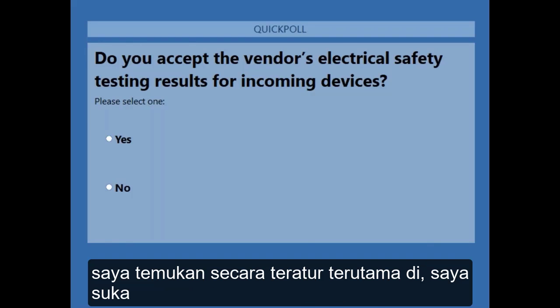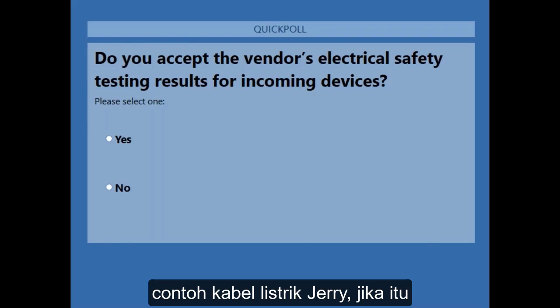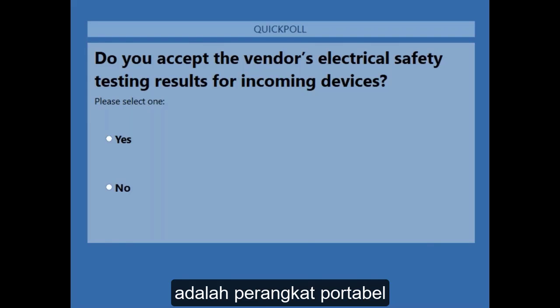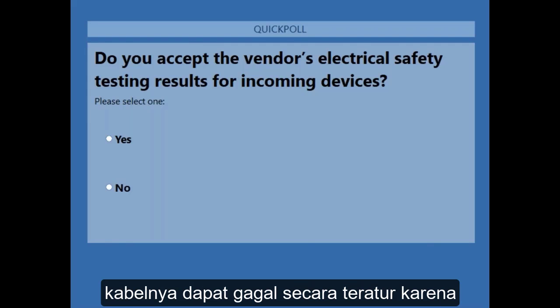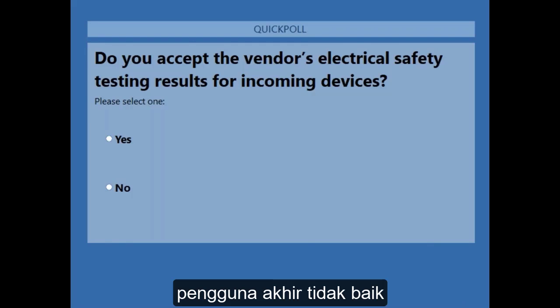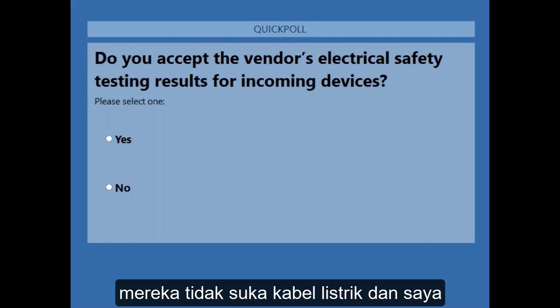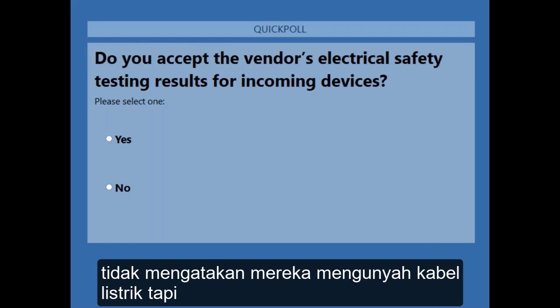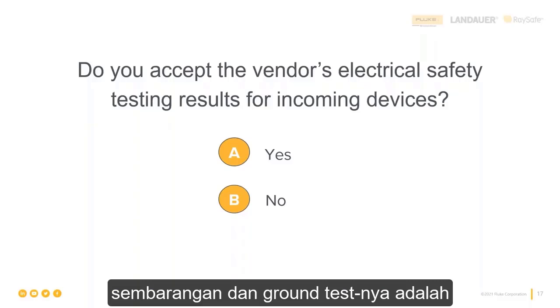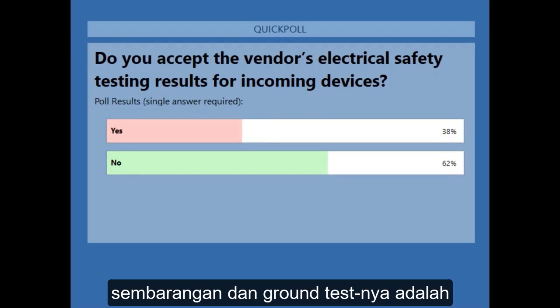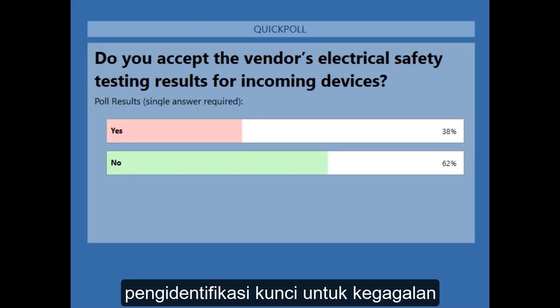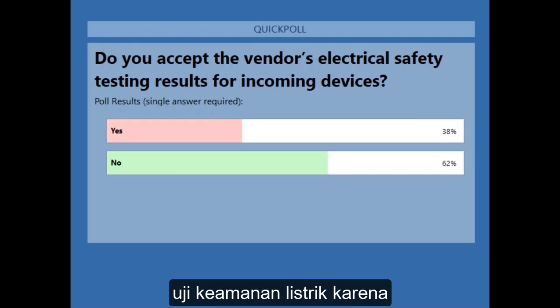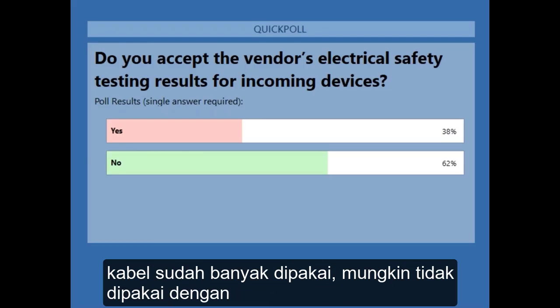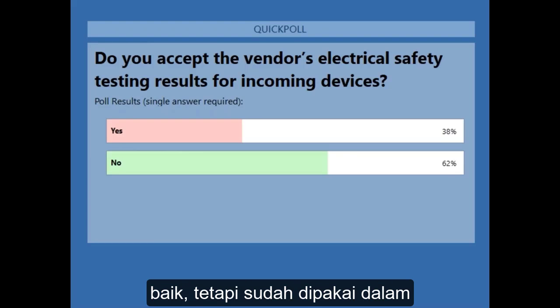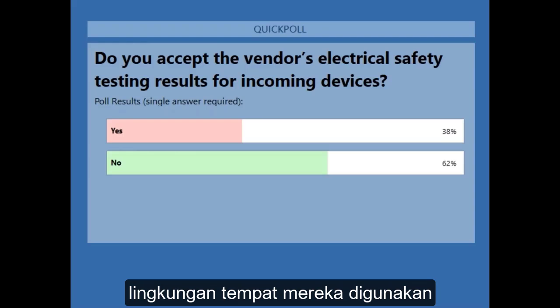One of the things I found regularly in the field, especially with power cords like Jerry's example - if it was a portable device, the cords failed regularly because the end users were not nice to power cords. I'm not saying they chew on them, but they would pull the power cords out at weird angles. So the ground test was a key identifier of failures in the electrical safety test, because the cords were getting used - not used nicely, but used in the environments they were deployed in.